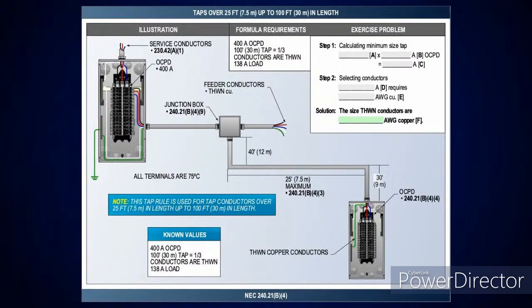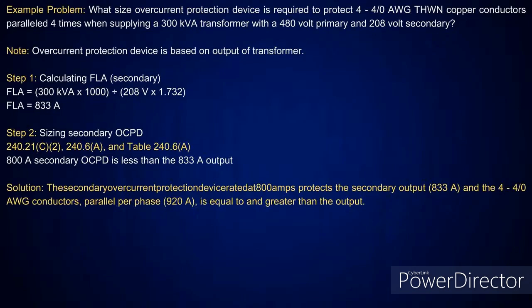But still, when I'm sizing the tap upstream, that 400 amps is taken at what? A third. Okay. And one thing to let everyone know if they're getting ready to take that test: if it doesn't say it word for word, if you're not following this word for word... I really appreciate this, James, because what you're doing is perfect. You're making it say it word for word. If you deviate from any of this stuff that James has on the screen right now, you're going to get it wrong, because it has to be word for word. It has to line up.